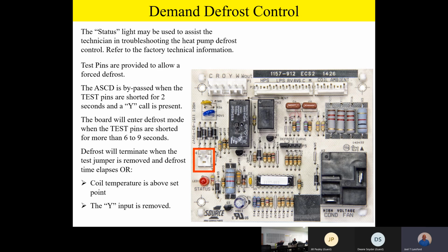But the thing with the test pins, now this is really important. The test pins right above that status light, if you jumper those test pins. Now remember, team, you can use anything to jumper those test pins. It's a low voltage, DC voltage. It's not going to shock you. It's not going to hurt you. So take anything. You could take a screwdriver, a quarter, a penny, a key. It doesn't matter.